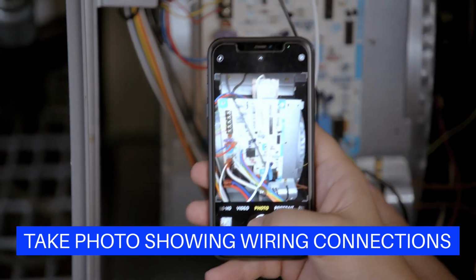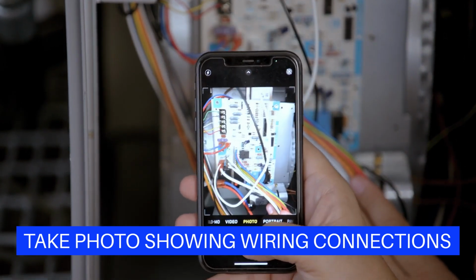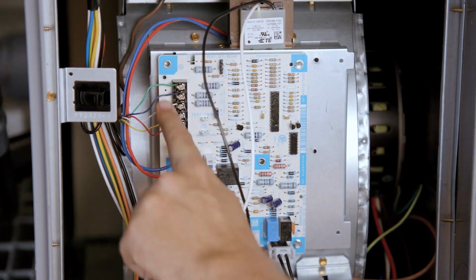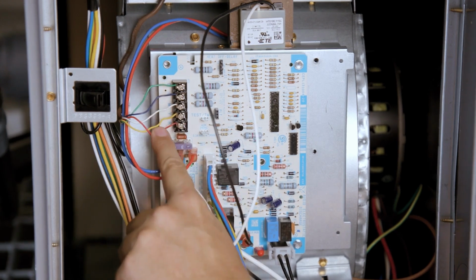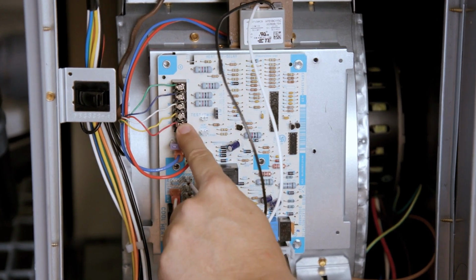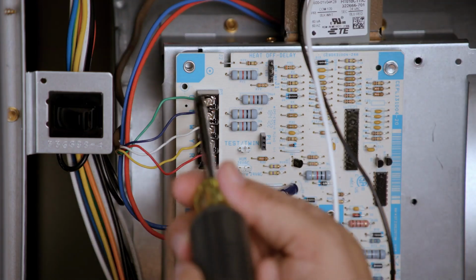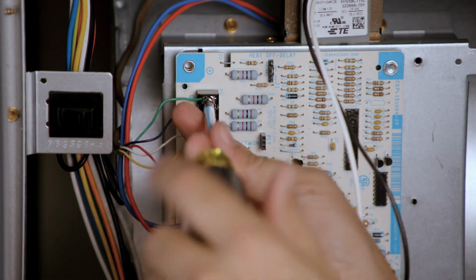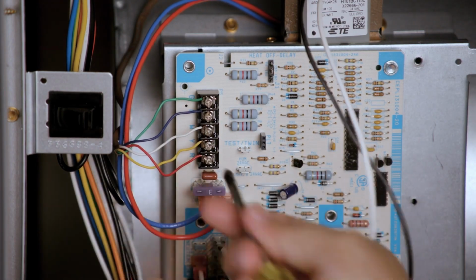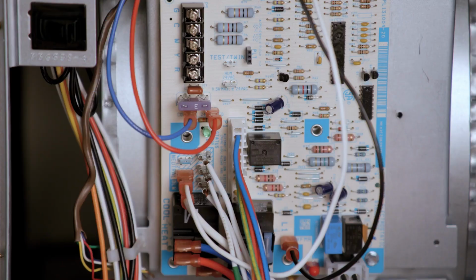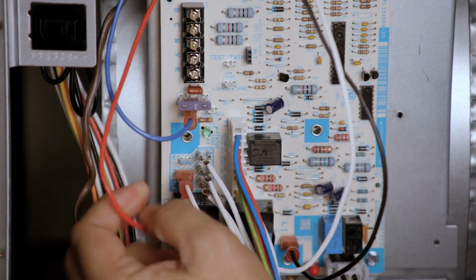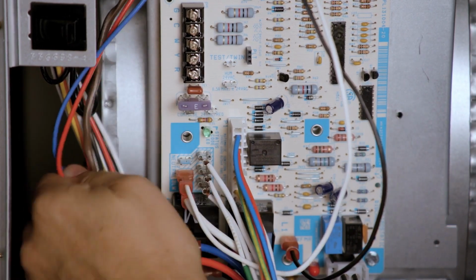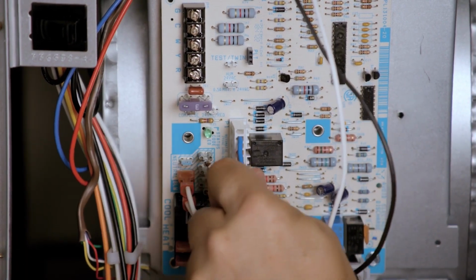Take a picture of the existing module for reference before removing any wires. Identify the existing wiring and take note of the terminal identifiers on the existing control. Disconnect the thermostat wiring. Take note of what color wires are going to each terminal. Remove the transformer 24-volt hot and common wires. Disconnect the 11-pin low-voltage inline plug.